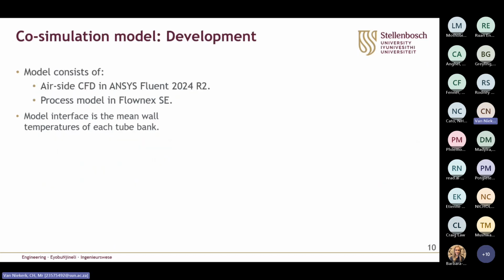the intercooler. So with the defined geometry, we can now integrate it into the co-simulation model, which consists of an airside CFD model developed in ANSYS Fluent and a discretized 1D heat exchanger network model developed in Flownex. And the main interface between these two models is selected as the mean tube bank wall temperature of each individual tube bank in the domain.